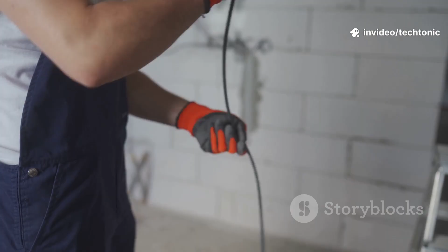Grounding isn't just for man-made electricity, it's vital for lightning protection. A lightning rod doesn't attract strikes, it provides a safe path to ground if lightning hits. Thick cables connect the rod to a deep grounding system, channeling the immense current safely into the Earth. Without this, lightning could destroy buildings and electronics.